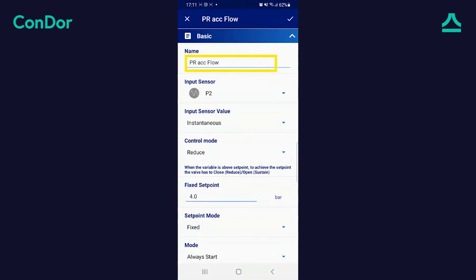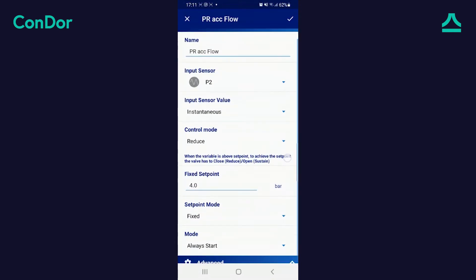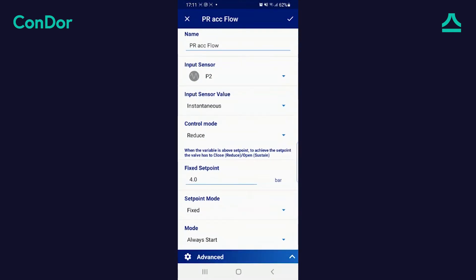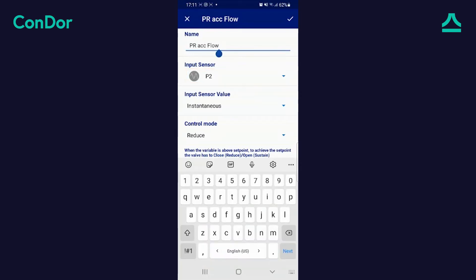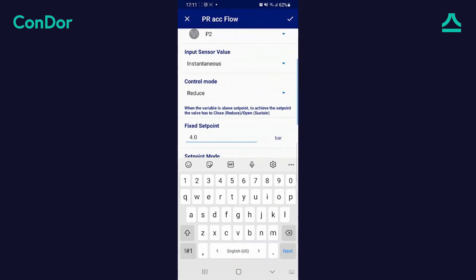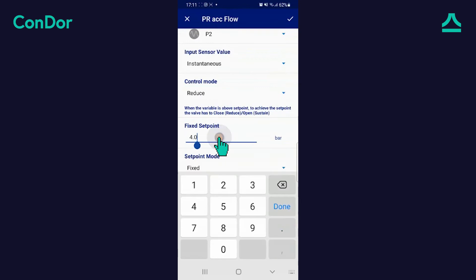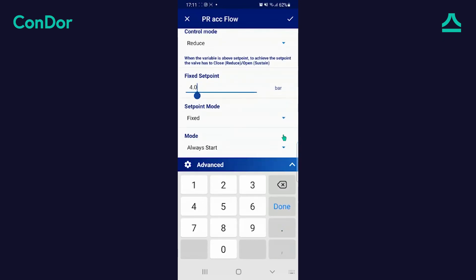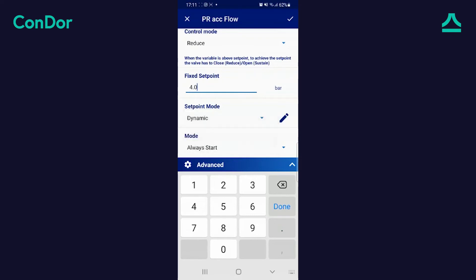The name of the function is fully configurable. Verify that the sensor measuring the regulated value — the input sensor — is correct. In this case, it is P2, the downstream pressure sensor. Select the setpoint mode and ensure it is set as dynamic. If it isn't, change it accordingly.